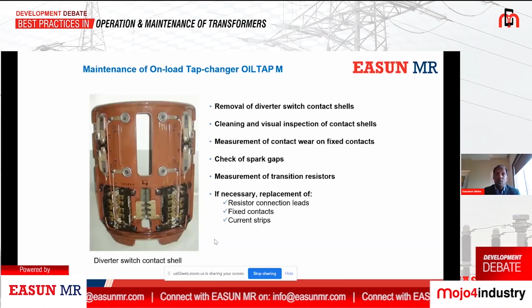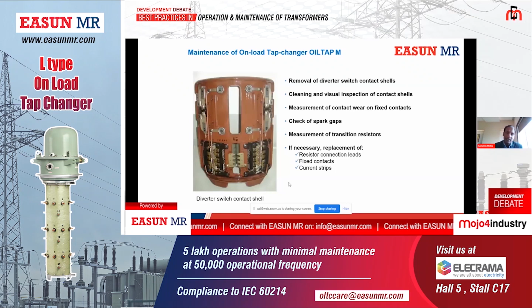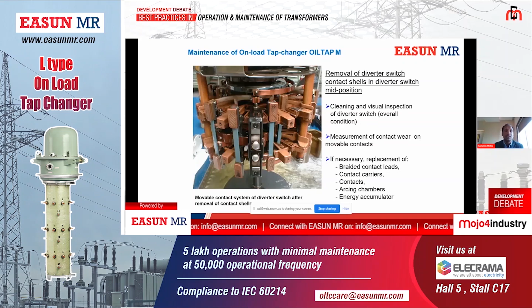But the point is always, what is the size? What are the torque levels? Each and everything will be known by the Easun MR tap changer service engineer only. Otherwise, if you are doing less tightening, less torque, definitely either it is going to get damaged or it is going to loosen during operations. Cleaning has been done, nicely cleaned, and each and every braid, contact, everything, the screw has been removed. This kind of maintenance is required at site.